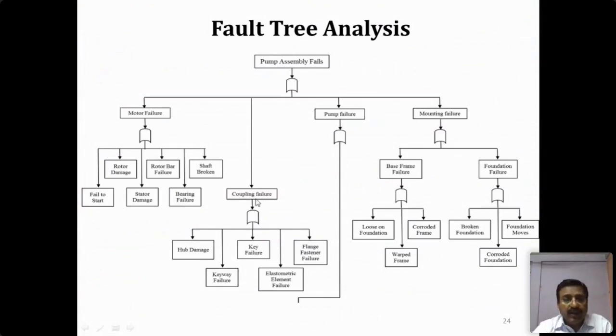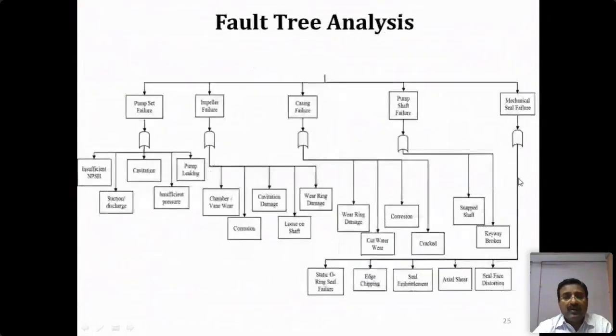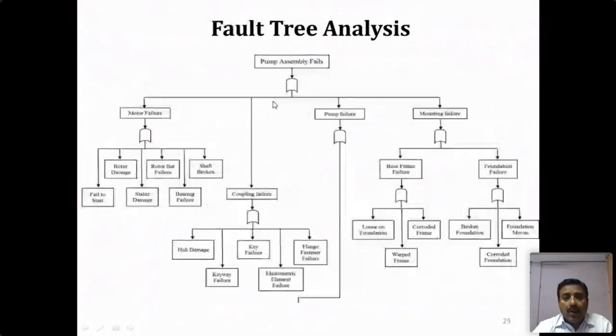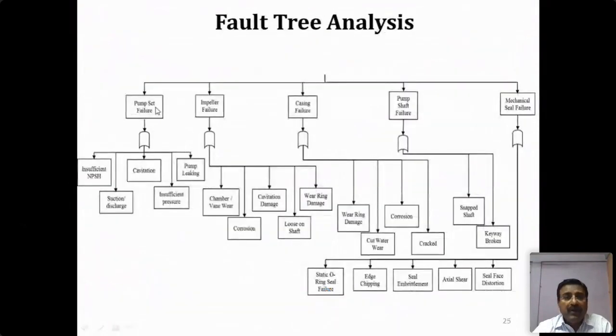When we talk about the coupling, then hub damage, keyway failure, key failure, elastomeric element failure, flange fastener failure. These are the possibilities for the coupling failure. Then when I talk about the mounting failure, there are again two options: base frame failure and the foundation failure. So you can think of it. Then here, the pump assembly failed due to the pump failure. How does the pump failure take place? The pump set failure, impeller failure, casing failure, pump shaft failure, and the mechanical seal failure. These are the possibilities of the pump failure.